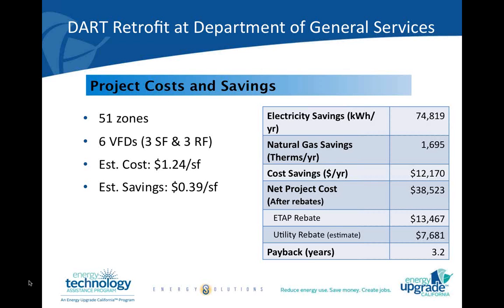All right, so for this building, we don't have VFDs in the facility. So part of the project cost is to go to the 3 units I mentioned earlier and add a VFD to the supply fan as well as to the return fans. In total, we have 51 zones. Looking at the energy savings, about 75,000 kilowatt hours per year, with cost savings of about $12,000 per year, and a net project cost of about $38,000. Once we get the rebates, the payback is a little over 3 years, which is really, really good for us.